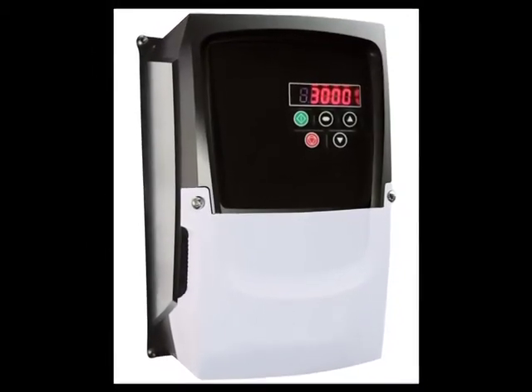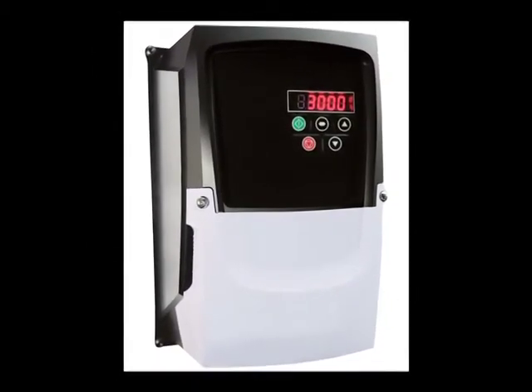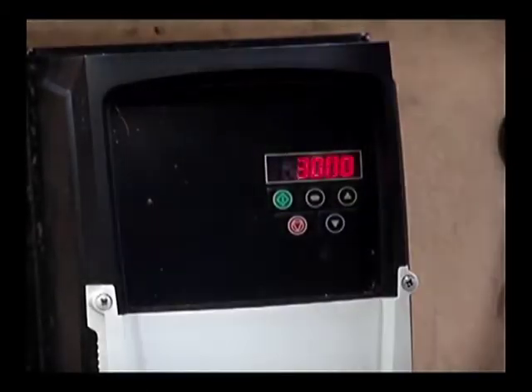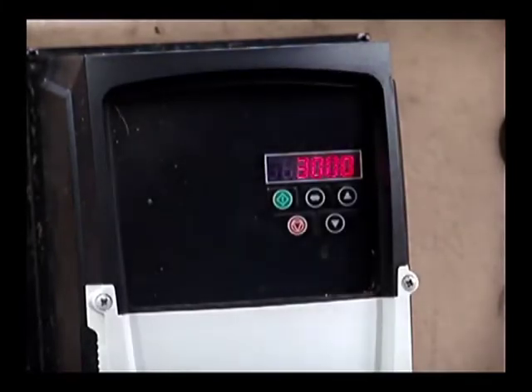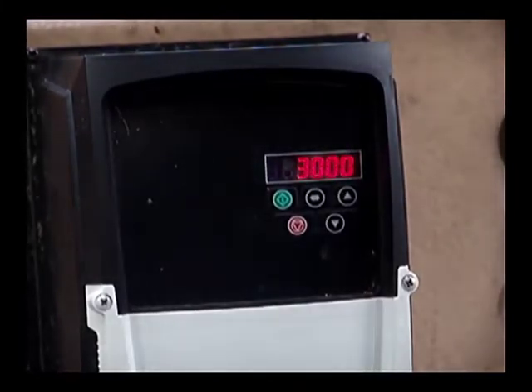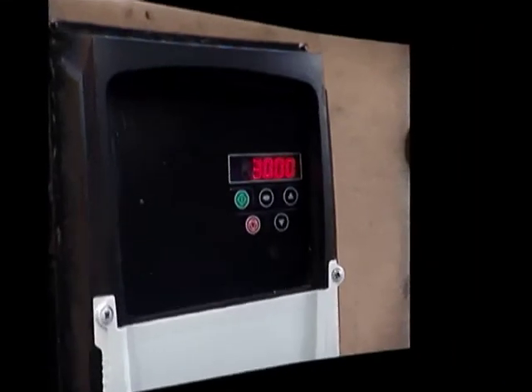It is really important to size your controller to the rating of the plate of the motor. I'm going to switch the unit on. The unit starts on a soft start and you can then see that the pump is running at 3000 RPM and at 50 Hz. What will happen now is your pump will run at that speed for 60 seconds. This is to ensure that your pump is fully primed and free from faults.